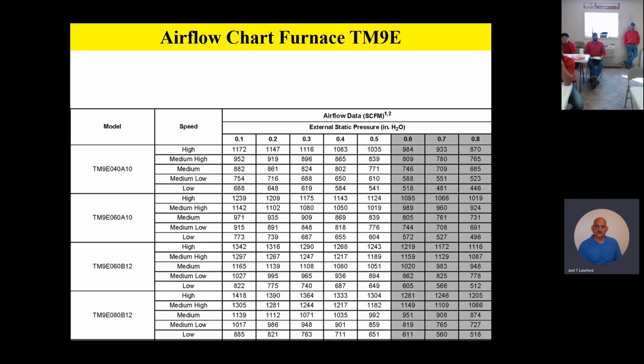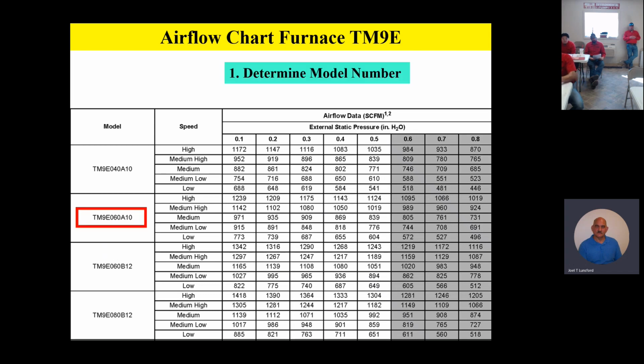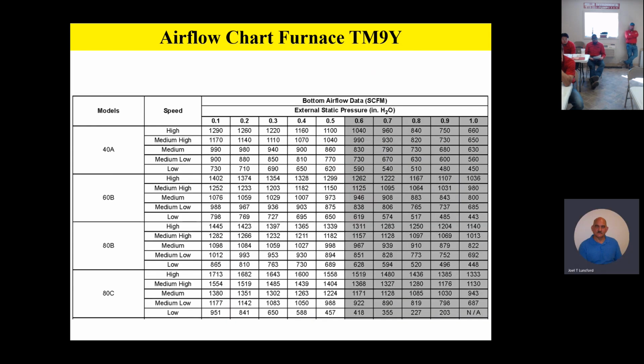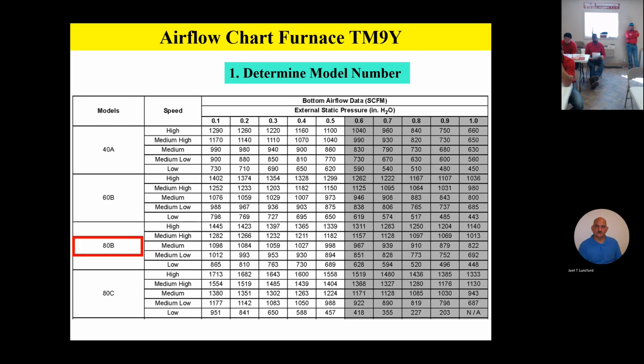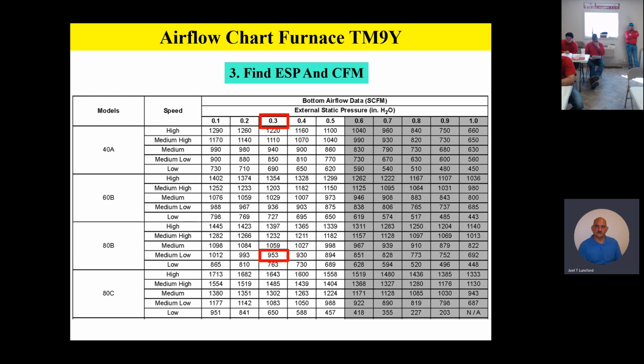All right, so look at your TME airflow chart on your furnace. Guys, it's the same thing. Step number 1, you find the model number. Step number 2, you determine what speed tap you're on. Step number 3, you find the static pressure and correlate it to the appropriate CFM. Same thing, but we'll do some examples just to make sure you guys have got all this. On the TMY furnace, same thing. You find the model number, speed tap, static pressure, CFM. Okay, so we're going to do some furnace examples, and then we'll answer any questions we have for you.